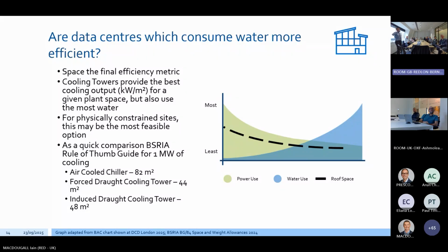Not only how much, if you use more water you obviously consume less power - again the point we just demonstrated - but also the space requirement goes down. So if you have a physically constrained site, let's say a colo located in a city location, you don't necessarily have enough space to put the data center where you may want. So you have to go up, and if you go up, you're then constraining your roof size, which limits the amount of cooling you can put on that roof.